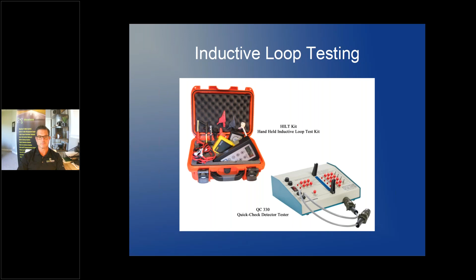The other product here is the quick check detector tester. This will do both shelf units—you can see the green MS connectors there for plugging into the 2 or 4 channel detector, and there's also a slot for the Caltrans style. The quick check is basically just for checking and setting the sensitivity levels on the detector. If you're not sure the sensitivity is measuring correctly, if it's not measuring down at the motorcycle level, you can plug it in here and very quickly check it. There's no software for this, no computers involved—it's all just push button. Same thing with the loop kit—no software involved, it just gives you a reading like a meter would.